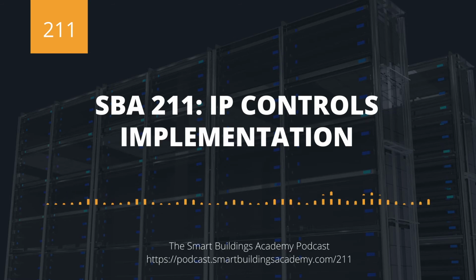All that being said, as I mentioned, star pattern is my preferred with terminal units coming off. However, with daisy chain, you can do a pattern where you daisy chain all of your rooftops, like 16 air handlers on the roof, daisy chain between those, and then terminal units off the MSTP trunks on those field controllers. That's a nice little pattern approach you can do. And then finally, there's ring.